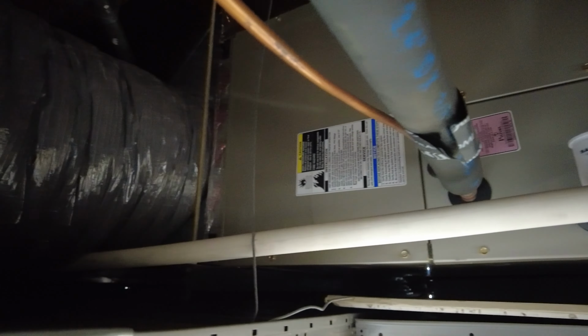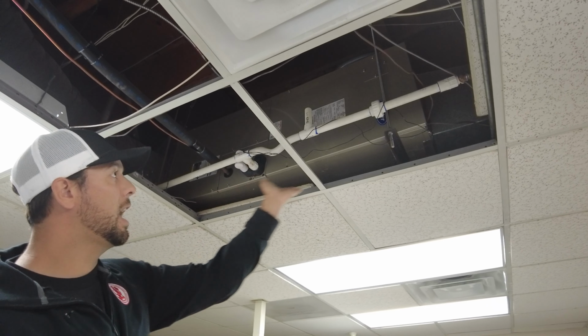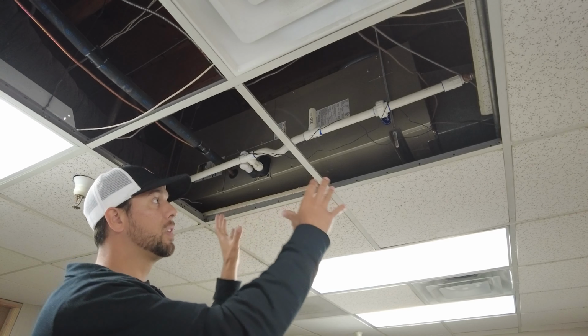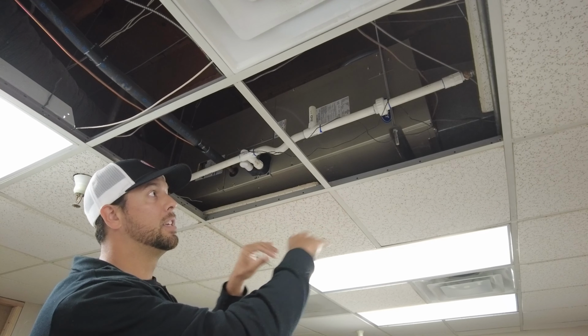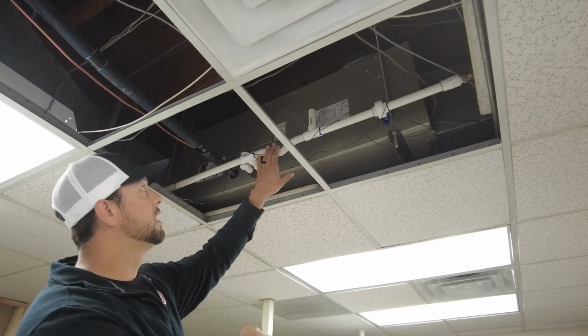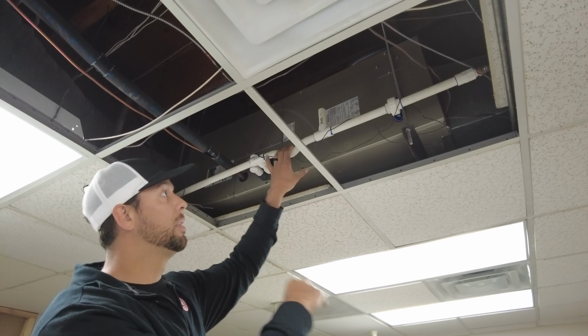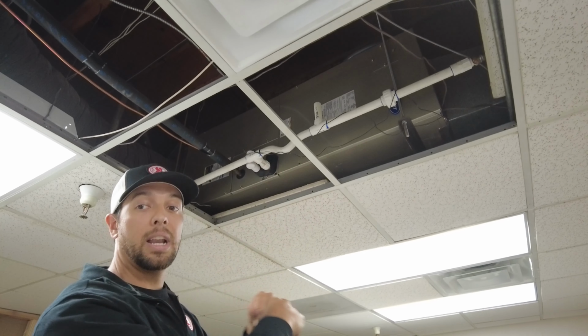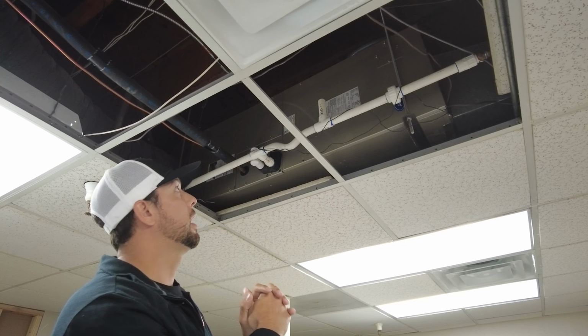We also want to take a look at our condensation lines. It actually turns to copper over here — we recommend that these be copper. It doesn't have to be, but this has a safety switch, though it doesn't have a catch pan. That would be something we'd want to recommend be added, so that if any issues with this condensation system started to happen, it would catch in the secondary and then be diverted to the exterior.